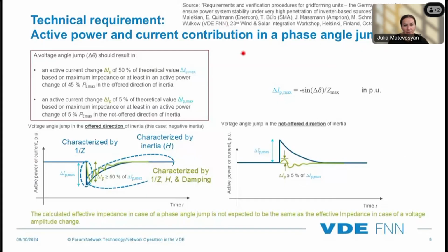So this slide is just fresh off the press. It came from the Wind and Solar Integration Workshop in Helsinki last week. And this is showing what's required by VDE FNN. As I mentioned, this document is specifying what grid forming resources providing momentary reserve have to do. And it says that in the beginning, when there is a phase jump, ideally there will be this first response that is only characterized by the effective impedance of the inverter-based resource unit.